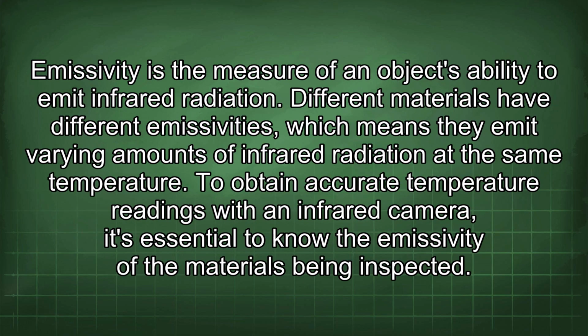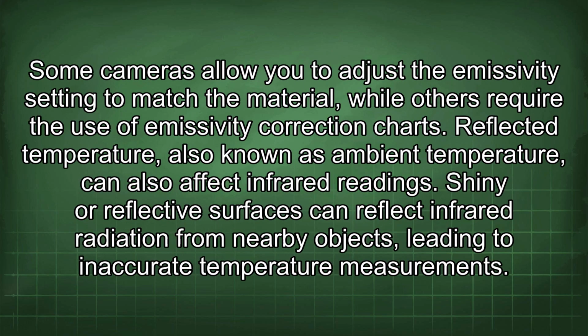Emissivity is the measure of an object's ability to emit infrared radiation. Different materials have different emissivities, which means they emit varying amounts of infrared radiation at the same temperature. To obtain accurate temperature readings with an infrared camera, it's essential to know the emissivity of the materials being inspected. Some cameras allow you to adjust the emissivity setting to match the material, while others require the use of emissivity correction charts.